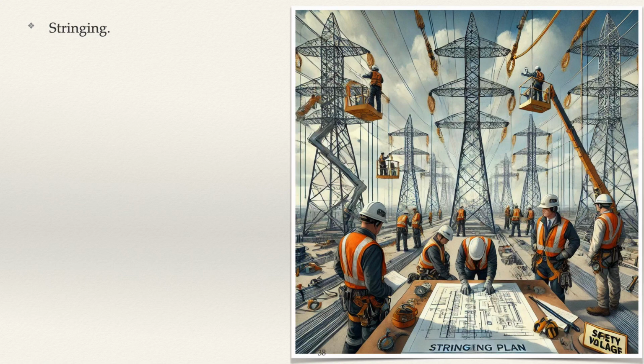Especially for optical ground wire, the purpose is mainly to ensure proper installation and testing of the OPGW, which serves as both a ground wire and communication line. And the key inspection focus would be firstly on OPGW jointing, by inspecting the jointing of OPGW cables, ensuring that fiber cores are correctly aligned and spliced to maintain signal integrity. Secondly, it's the end-to-end testing, by conducting tests using optical instruments like an optical time domain reflectometer, OTDR, to verify that the OPGW is free from signal loss or faults.